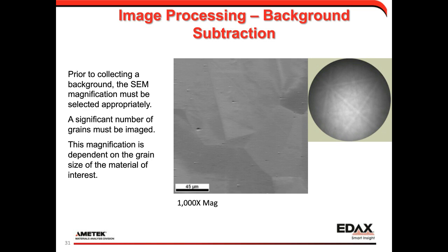That's the danger of doing large grain specimens and taking a background at the wrong magnification. So when I do that, again, I usually zoom out by about a factor of 4. If you're using the optimization routines, they will automatically zoom you out by that factor of 4 to account for that. There is a danger with the optimization routines in taking a background if you're near the edge of your sample. If you're near the edge of your sample, you zoom out.